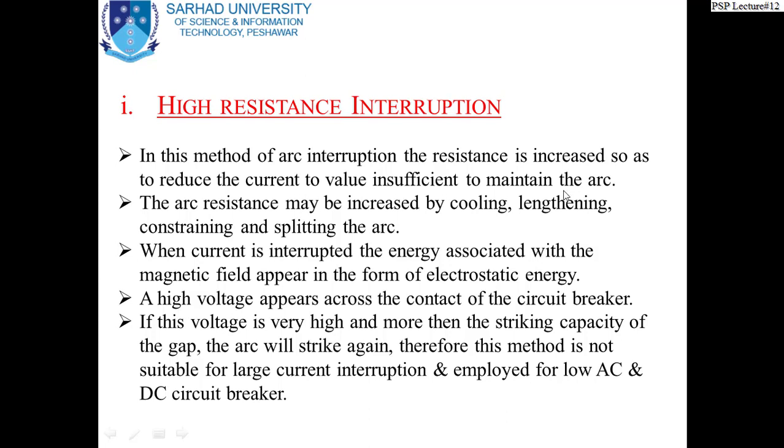Now, gentlemen, you see here to maintain the arc, a certain amount of current is required, right? So, if we increase the resistance between the two contacts, the current will naturally be decreased, because increasing resistance decreases the current, simple Ohm's law. So when the current decreases beyond a certain limit, it is unable to maintain that particular arc, so the arc will be extinguished.